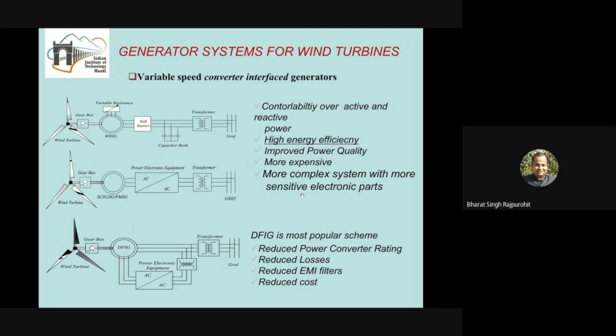But we are slowly seeing that the new wind turbines coming in are based on variable speed systems, and generally they use mechanisms by which the speed can be varied, either by using a power electronic converter or by some alternate mechanism. The literature says that with a variable speed system, in which generator speed can be varied in a broader range, the energy coming out from the moving or varying wind is higher. Some data says that, based on the site, it is 9% higher as compared to a fixed speed system, and somewhere it even goes up to 40%. So in a nutshell, the difference between fixed speed and variable speed systems is that by utilizing a variable speed system, more energy can be captured from the same wind. It means the energy output of that wind farm would be higher if it is using a variable speed system. Any query in this case, then please let me know.